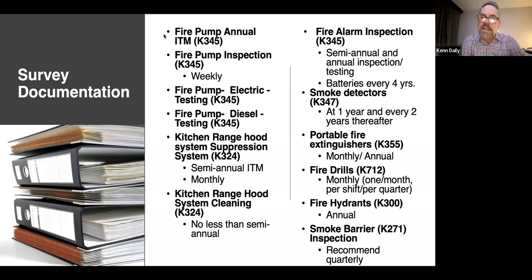Kitchen range hood has not changed. It's still every 6 months you have your kitchen range hood inspected, tested, and maintained. And that's again a tag system like your riser room for your sprinkler system. It's another extinguishing system that is tagged and is done every 6 months. And then your range hood cleaning, which is also no less than every 6 months, which is your range hood from the hood going up through the roof is cleaned down to the bare metal.